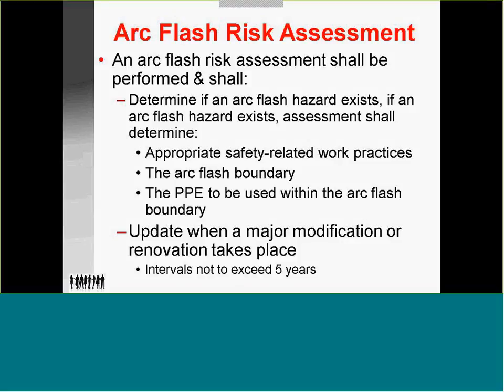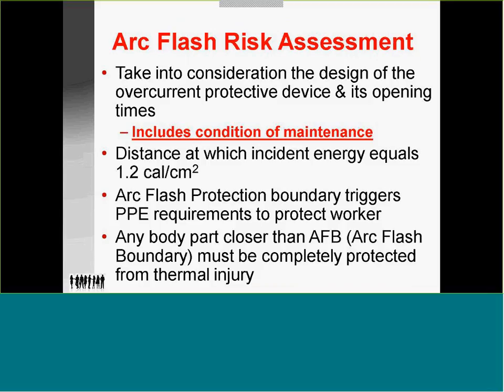The study must be updated when a major modification or renovation takes place, but not to exceed 5-year intervals. The reason being, if you're in a plant that's isolated out in an industrial park, and that's the only plant out there, the grid is lower in capacity. But as more factories are built into that grid, it starts changing. More amperage is being supplied into that area, and that must be taken into consideration. Fault current coming off the grid must be known to make the arc flash calculation inside the property.